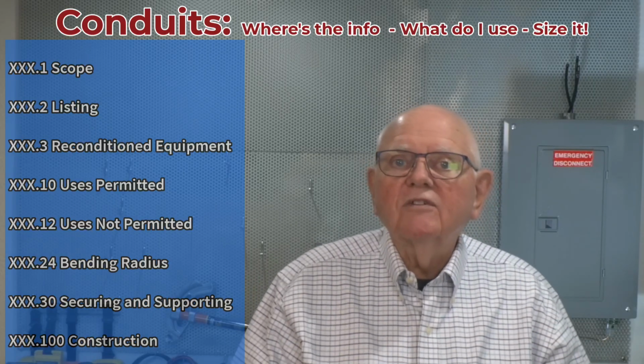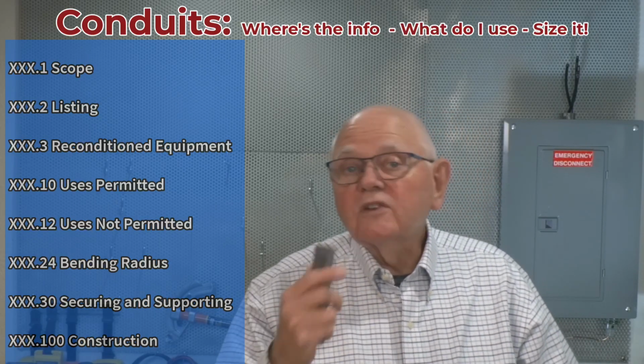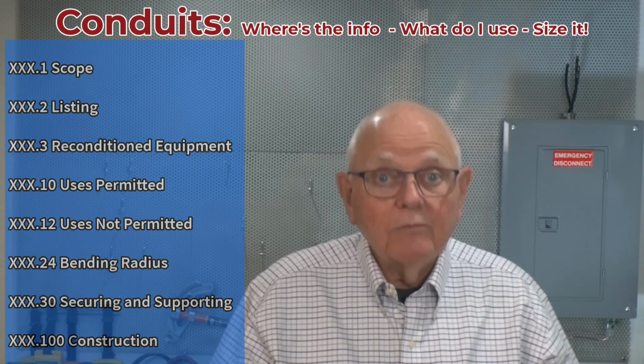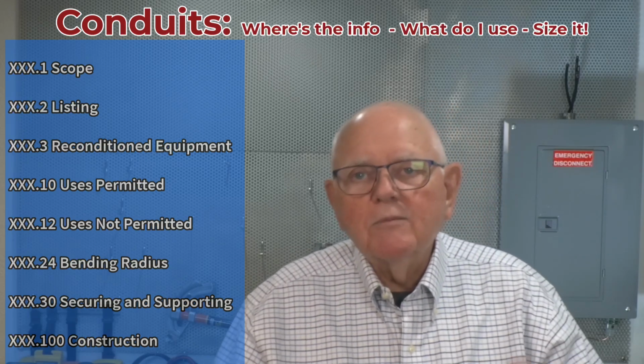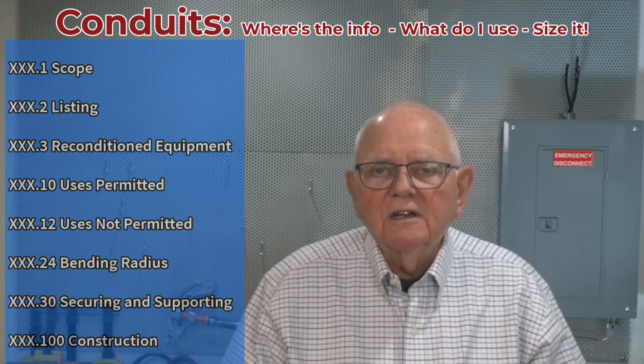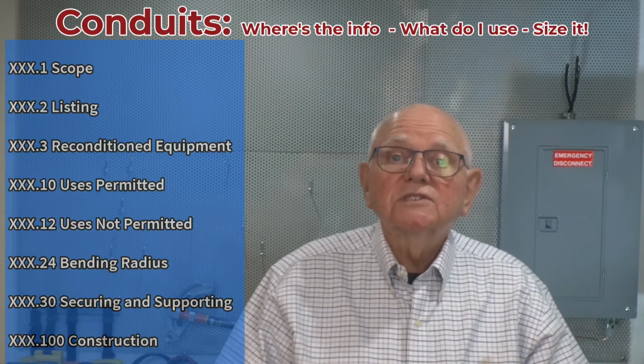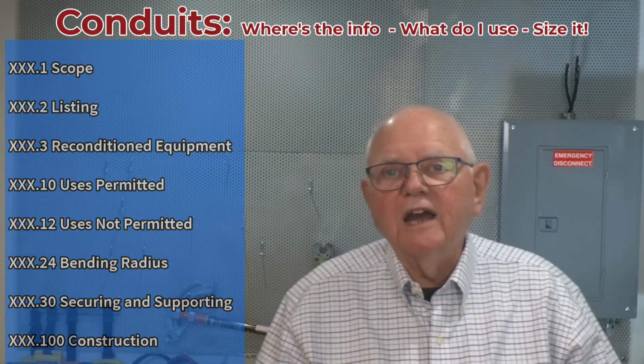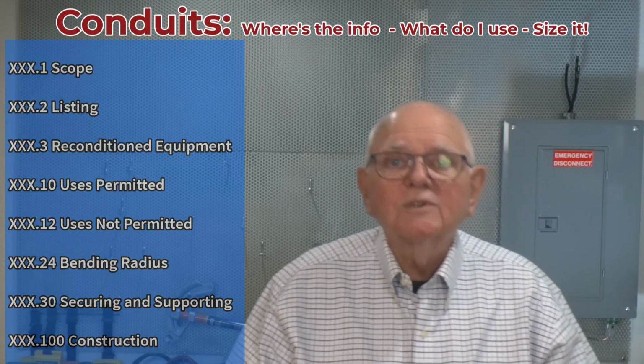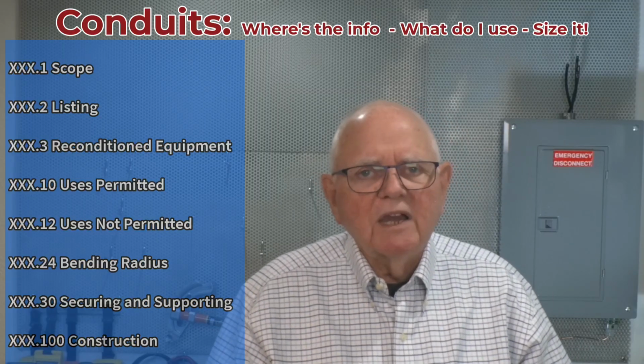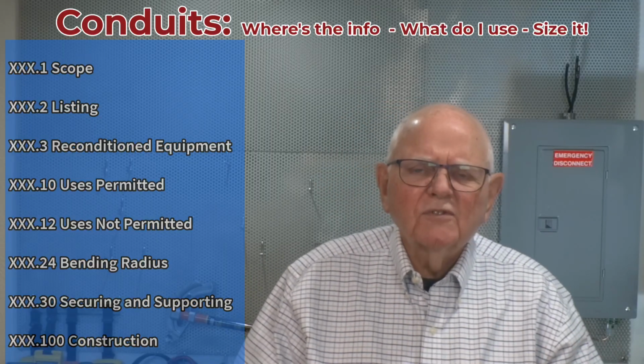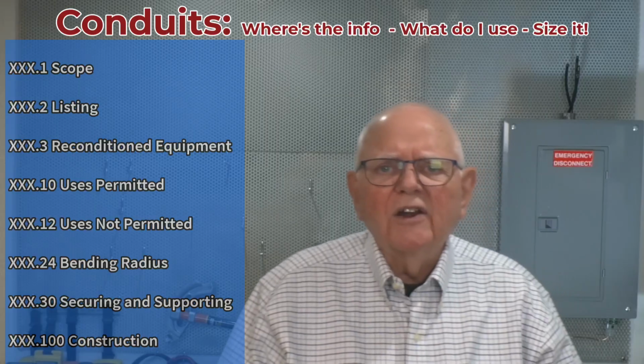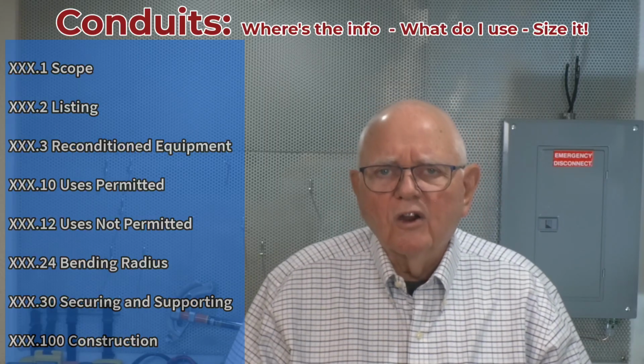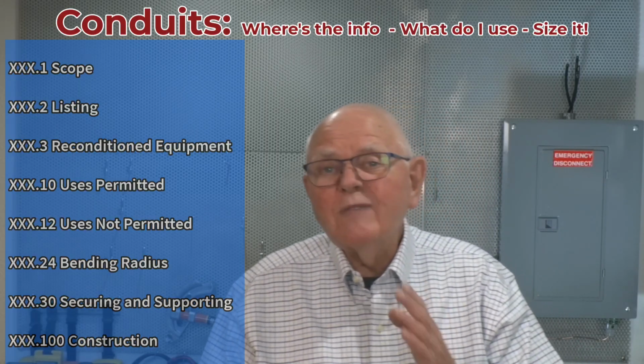Bending radius is covered in .24, as well as a table in Chapter 9. Table 2 in Chapter 9 gives me my bending radius for different size conduits. .30 is securing and supporting of those conduits. And .100, which is Part 3, is my construction, usually fairly short sections on how that particular conduit or tubing is constructed. So that makes it a lot easier.